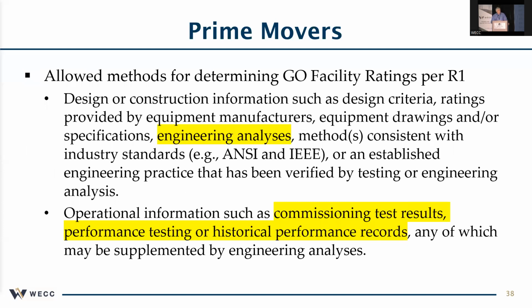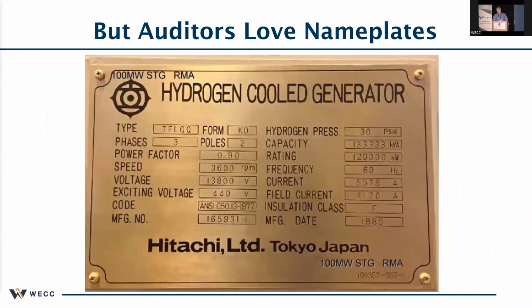Allowed methods for determining facility ratings. This is just a read for R1: even if we said you can't do this prime mover consideration, if you did an engineering analysis, commissioning test results, or performance data, and that prime mover was actually your limiting value, that's going to show up as your limit, even without doing a horsepower conversion. But we do love nameplates. We don't like those engineering values.